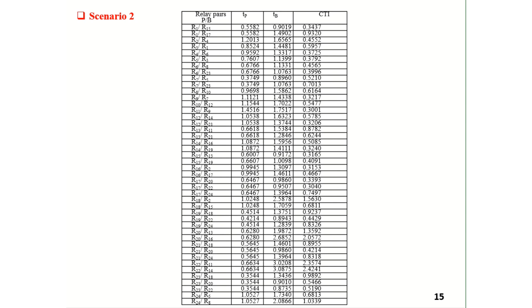The results of the calculation of primary and backup relay operating times with the new TDS and PS settings and the calculated CTI of all primary backup relay pairs are given in this table. It's clear that the CTI is greater than 0.3 seconds for all pairs of primary backup relays. We can deduce that the application of the genetic algorithm on this distribution network can solve the coordination problem in the presence of distributed generators while respecting all constraints.